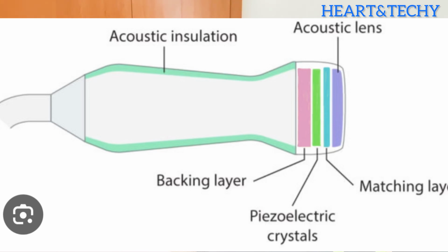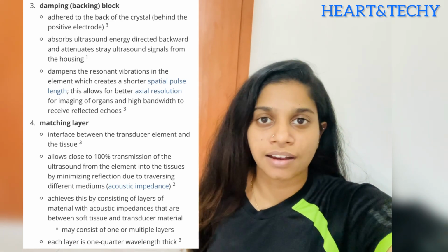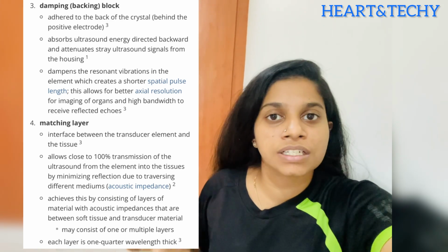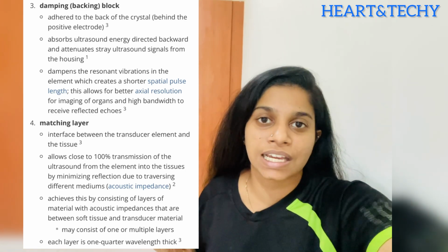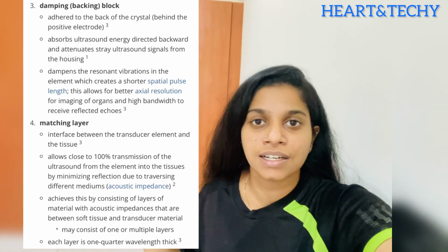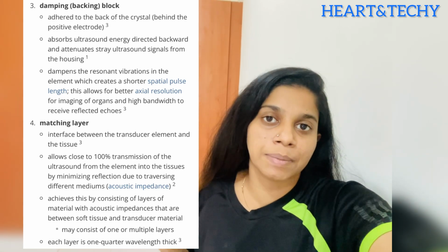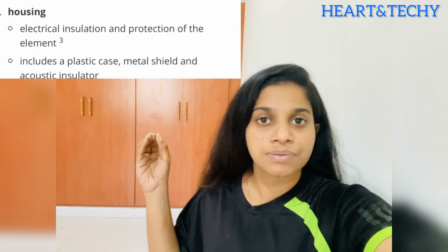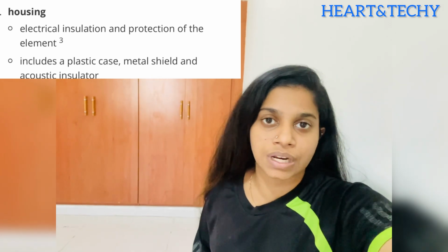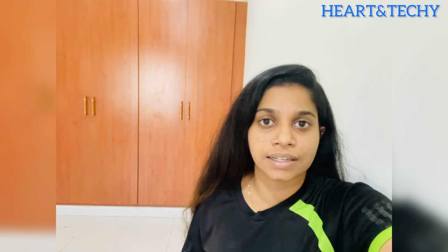It has insulation, acoustic insulation, and a cable which helps to deliver the electrical energy to the probe. It has a matching layer, backing material, and the piezoelectric crystal layer inside. The insulation helps to prevent electrical shock between the operator and the probe. There will be a matching layer and a backing layer. I'll give these features on the screen, and we will explain them in the next video.